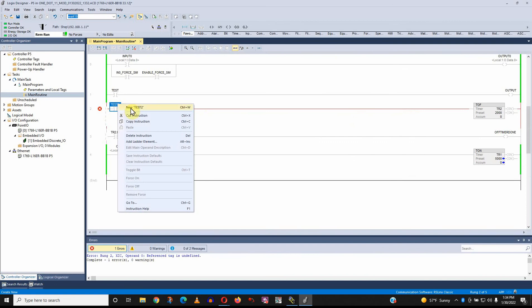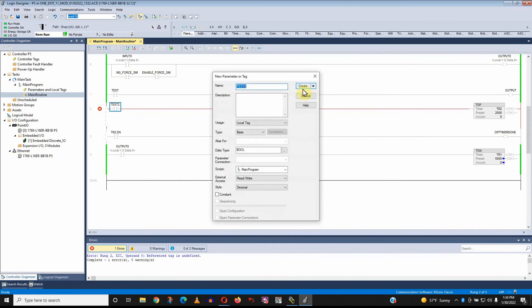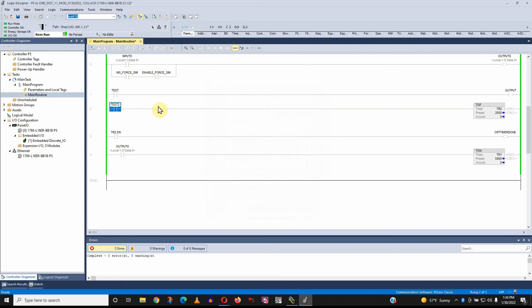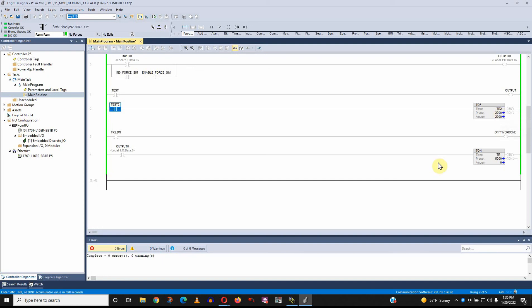Something didn't go right — test two. I have to create a new test two. When you see a red rung here, red means it's broken — you'll need to fix something on there. The processor is running. I'm going to right click on test two to activate it, and you'll notice the timer done bit came on — off timer done is now true. If I open that contact, it starts to time out and then turns off. So it's an off delay timer. You don't see a lot of off delay timers, but they're very handy. You can work around it with an on delay timer, a TON, but sometimes it's just easier to use the TOF.